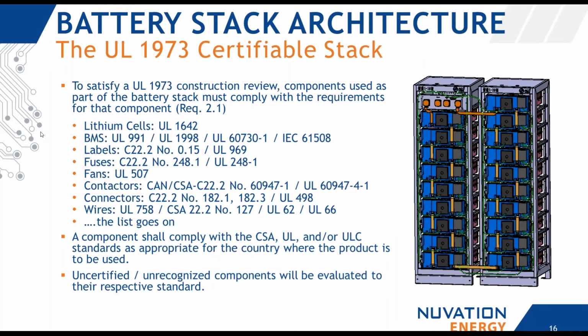In fact, part of 1973 requirement 2.1 says that all components used as part of the stack have to comply with the requirements for that component. To list a few of these, it's not an extensive list by any means, there's a lot more than this: lithium cells UL 1642, fuses, so that's the CSA spec or the UL spec for 248, fans UL 507, and it just goes on. Any component shall comply with the CSA, UL, or ULC standards appropriate for the country where the product is used. And uncertified or unrecognized components will be evaluated to the respective standard.